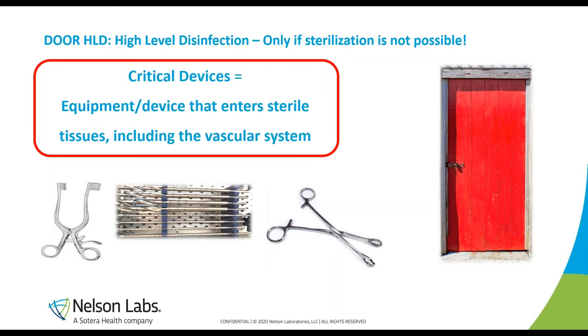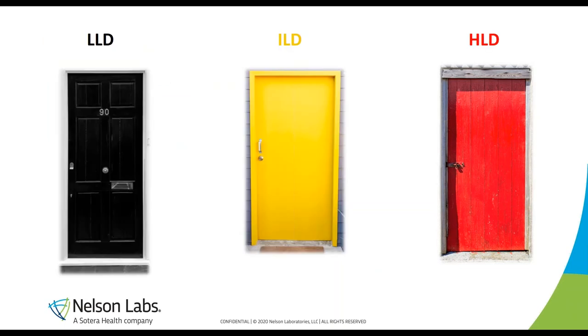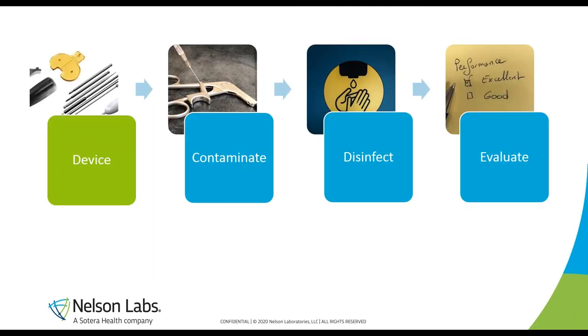Sometimes a material is not compatible with sterilization and you can only rely on high-level disinfection. Regardless of which door you enter — black, yellow, or red — the setup of your disinfection validation can be split into four parts, all the same for the three levels. This gives you a main validation framework you can use across all disinfection levels, making it easier for everybody.